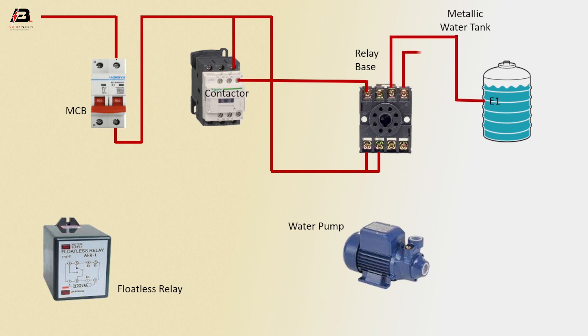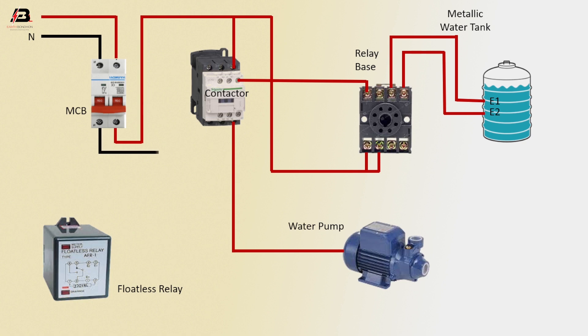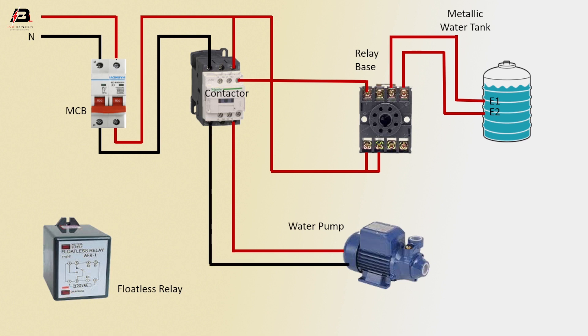Phase connection from relay to connect water tank E2 position. Phase connection from magnetic contactor to connect water pump. Neutral connection to MCB circuit breaker. Neutral connection from MCB circuit breaker to connect magnetic contactor. Neutral connection from magnetic contactor to connect water pump. Contactor coil connection to connect relay. Earthing connection to water pump.